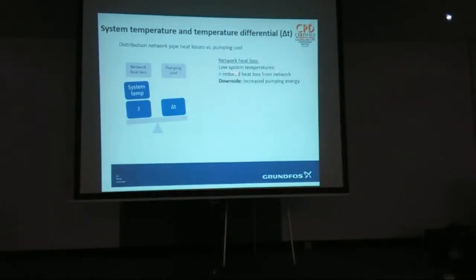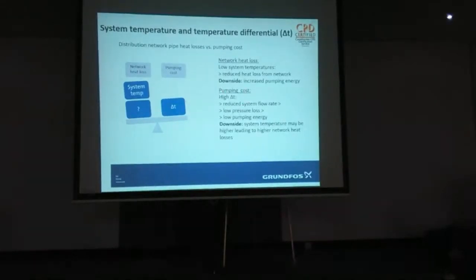If you have lower system temperatures, you lose less heat, I suppose. Right, rework that. If you have a lower differential temperature, I read it this morning. Lower differential means a higher flow rate in volume, which means a higher resistance, so you need more pumping power. If you've got a higher delta T, a wider gap, 30 degrees, 40 degrees, you've got a lower flow rate. If you've got a lower flow rate, you should have lower resistance, which means a smaller pump, less energy.